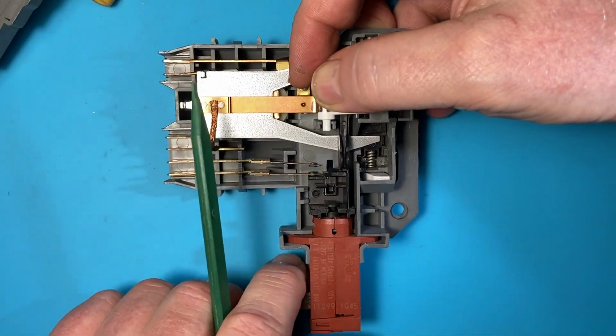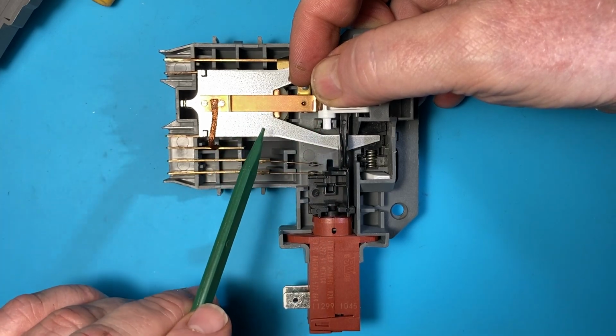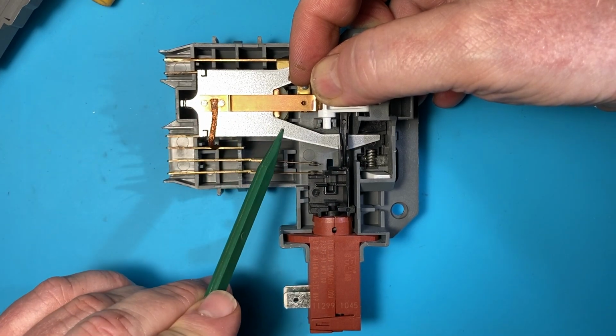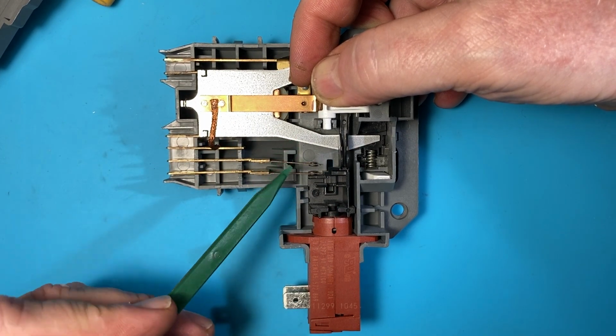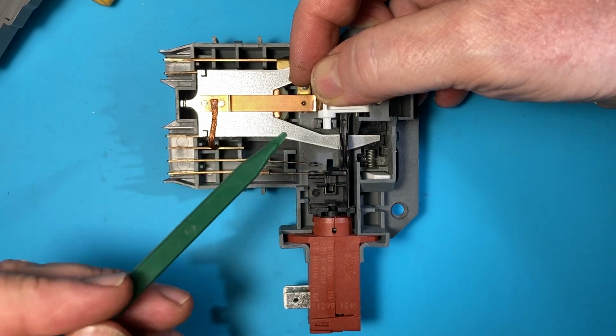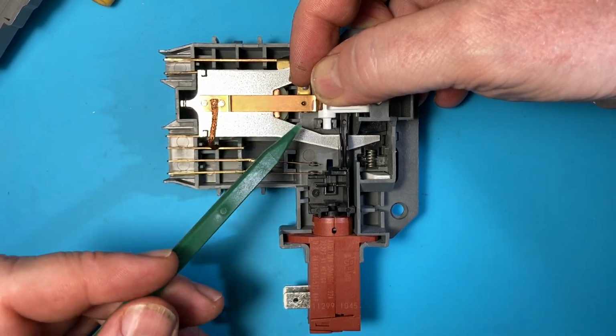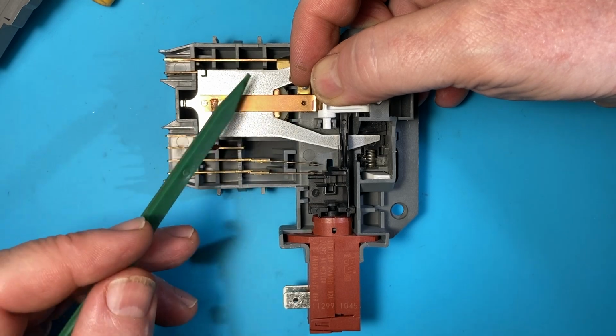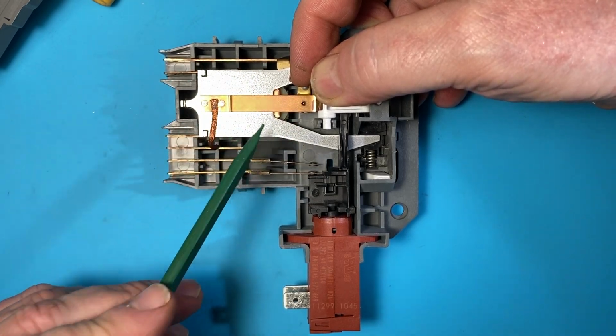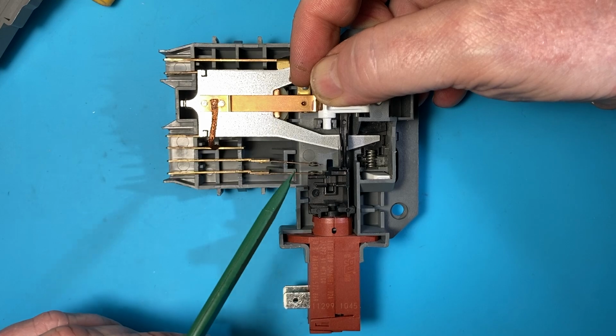So imagine the power goes out, and this is all the way up, and this spring would like to pull the locking fork up and open the door closed signal. So the door closed signal is only valid when the relay is energized. That's a fine point.